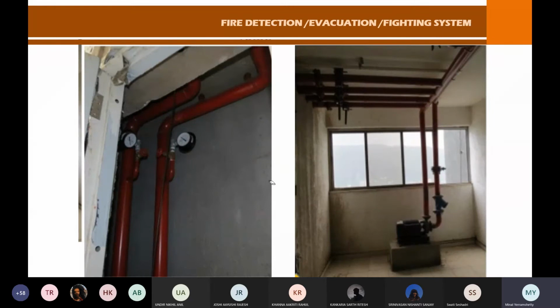These are the kind of booster pumps that are put in place, connected at the top level. It's hard to tell if this is a sprinkler line because the size is smaller - both could be sprinklers, it depends. As the height increases, the sprinkler pipe sizes will also increase. It won't remain 3 inches or 75mm as I told you before - it can even go up to 6 inches, because you need more pressure and there are too many zones to cater to, too much water needed, so the sizing increases as per the size of the building. You can see the usual barometers, pressure gauges, thermostats - every sensor is installed, and all this is linked to the BMS.